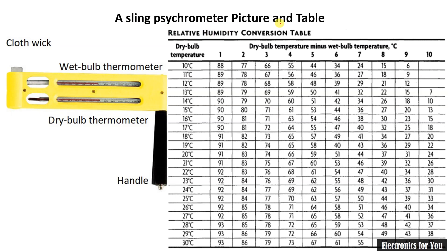This is a sling psychrometer picture and you can see the relative humidity conversion table. Let's say the dry bulb temperature is 20°C and the wet bulb temperature is 16°C. We find the row for dry bulb temperature of 20°C. The difference between dry bulb and wet bulb is 20 minus 16 equals 4°C, so we look at that column. The intersection of this row and column indicates 66% relative humidity. In this way we can measure humidity using a sling psychrometer.